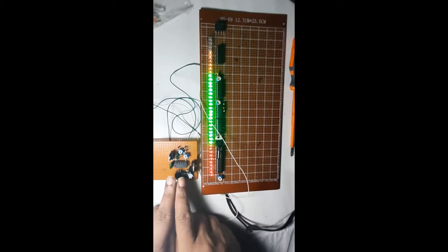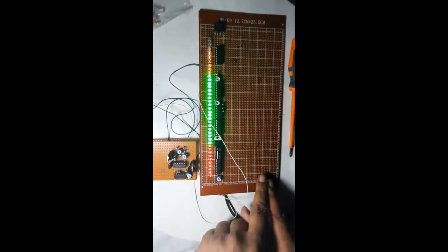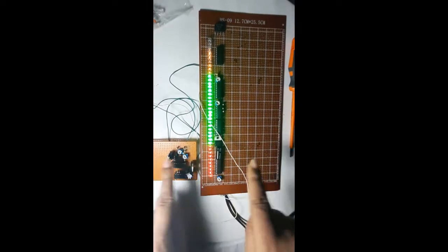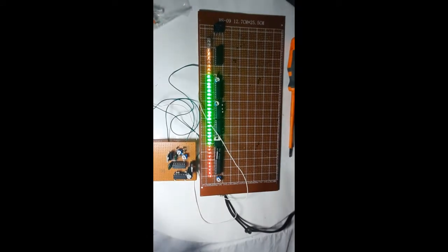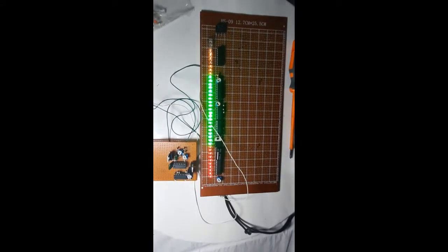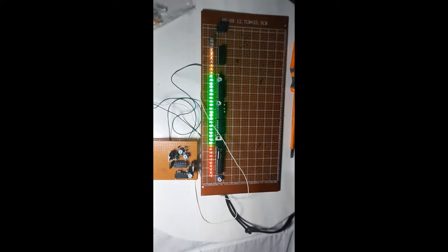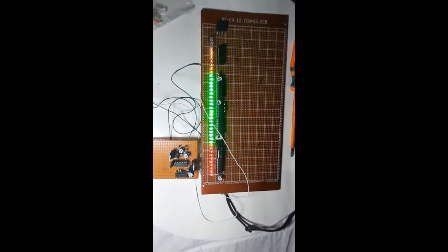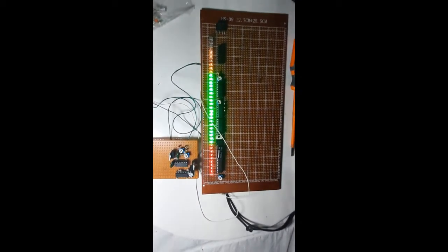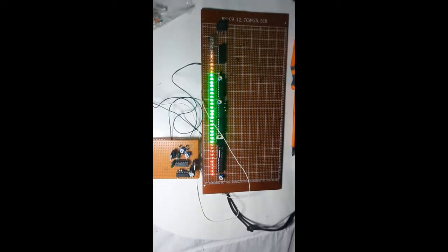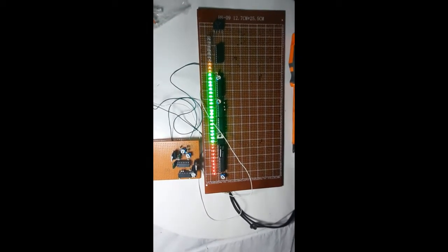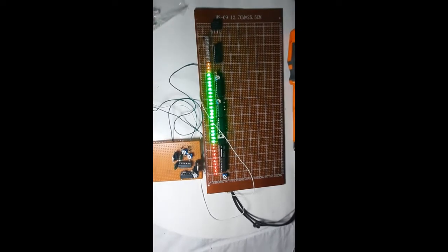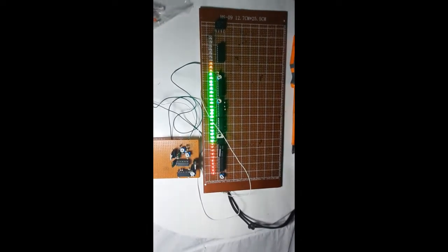So now the 4-20 milliampere signal is generated here and given to the receiving end. These two devices might be 300-400 meters away from each other, even more than that. Now you know that one of the highest advantages of the 4-20 milliampere signal loop is that it is immune to external voltage variations like induced voltage, and to the variation of the resistance of the cables due to temperature, especially when the cables are long. So the 4-20 milliampere signal loop is immune to those.